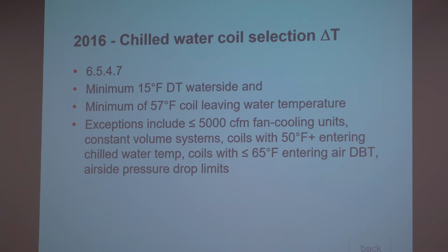This came out of a desire by some progressive folks to at least require 6-row cooling coils. That isn't exactly how codes get written, because we're not trying to prescribe a solution, we're trying to prescribe a performance level. So in order to get the pump savings that we want to get without having to prescribe a specific type of coil, we instead specified a range for that coil. So a delta T, or a flow rate, essentially, minimum delta T, essentially of 15.